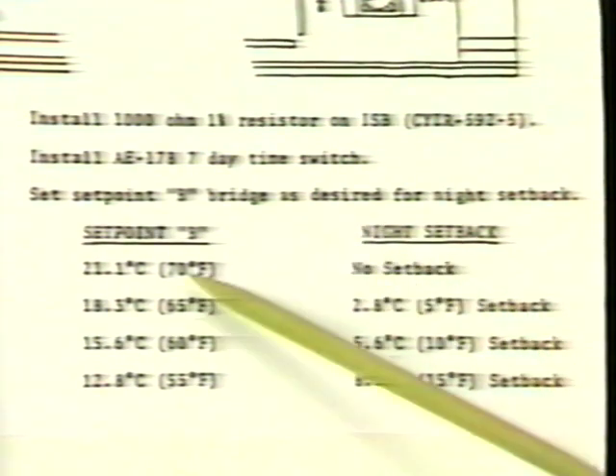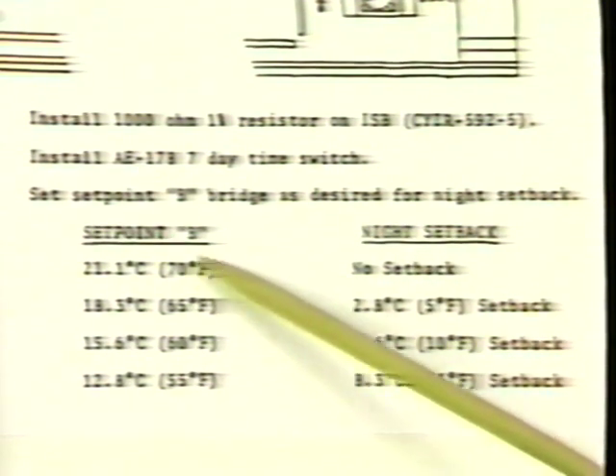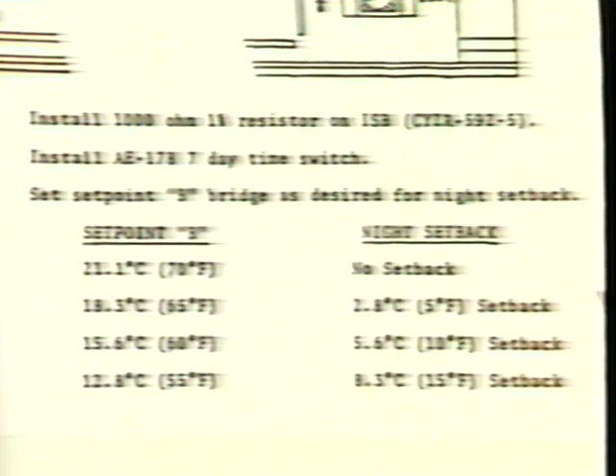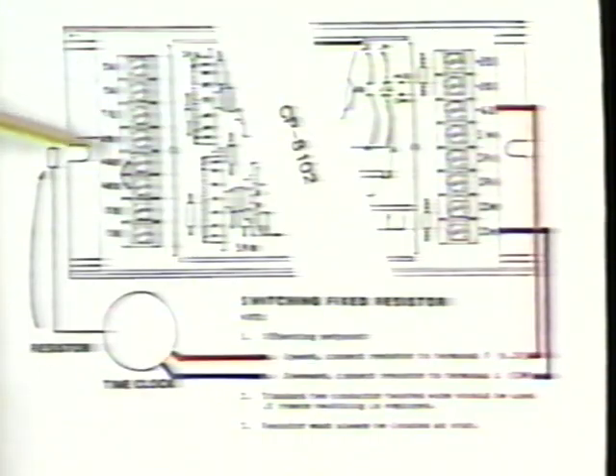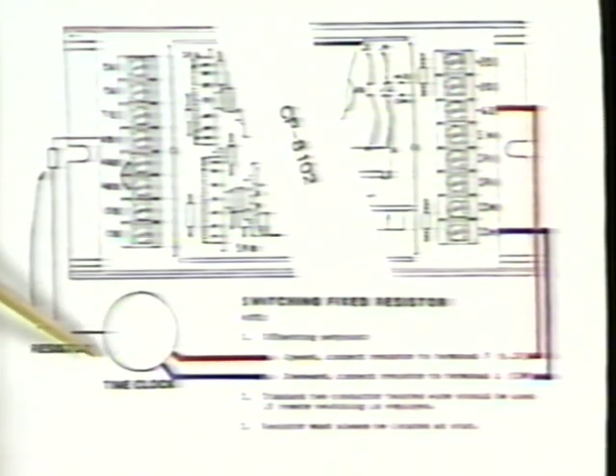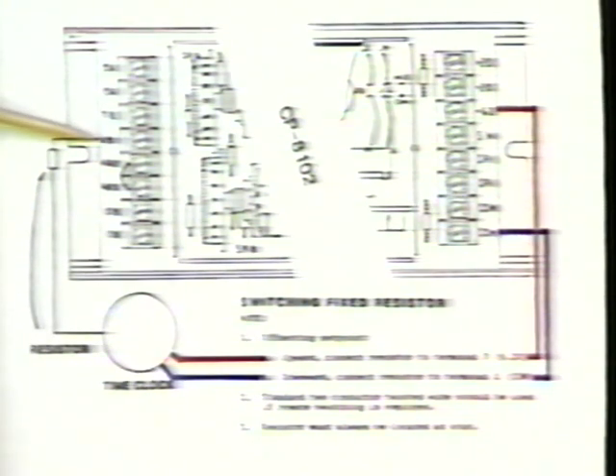In addition, if set point B is set above 70, that will create a set forward effect in set point A. Finally, the ratio adjustment for the controller must be set at 1 for this application. And the type of reset required, as determined by the action jumpers, must be reverse reset. In this example of reset, ISB is not available. Instead, a fixed resistor is used in a circuit made and broken by a time clock between AB1 and either 6.2 volts or common.